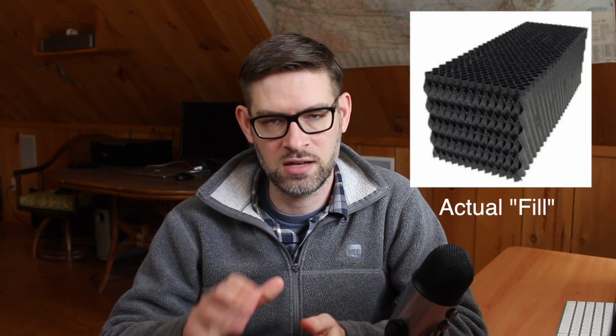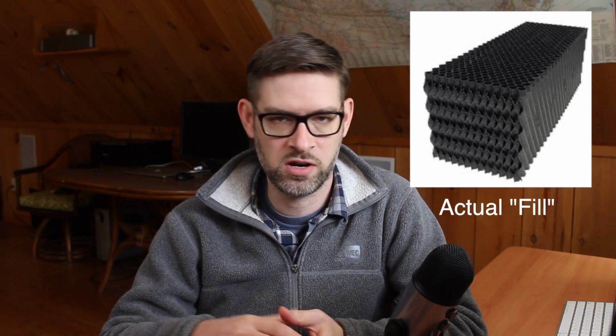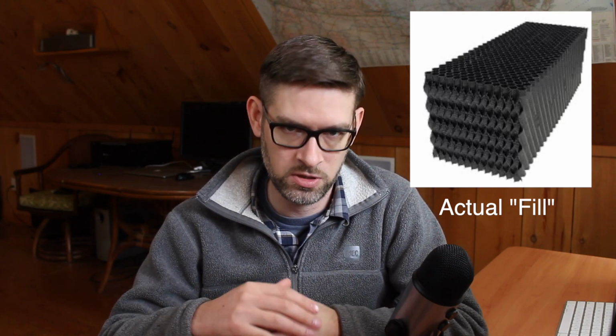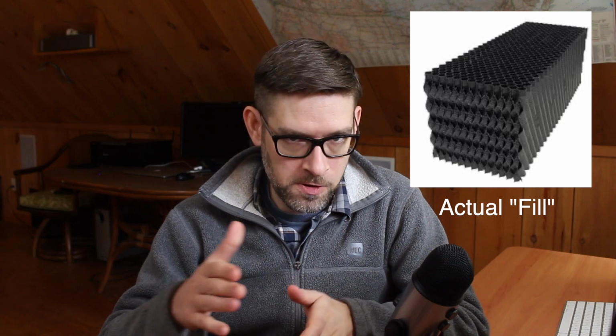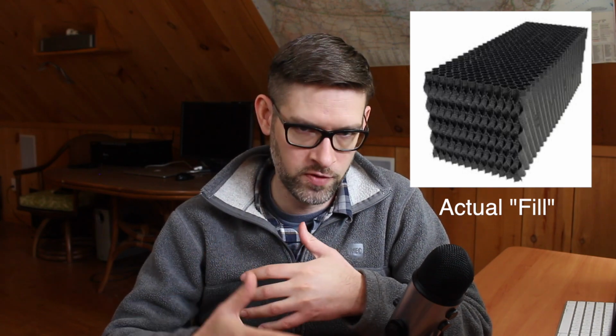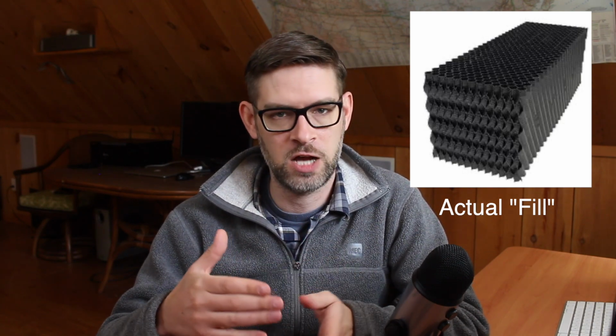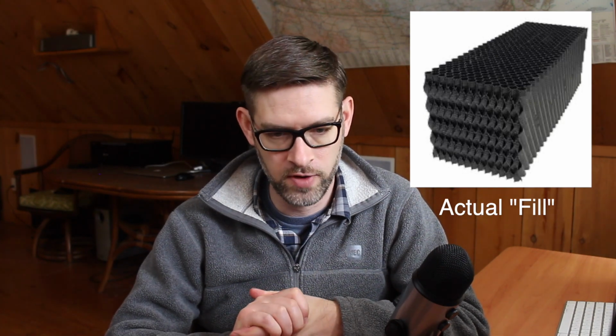Now, the fill most commonly today is a film style fill, and it's designed to provide a large surface area for the working fluid to flow over. A film of water is formed on the surface of that fill, which allows for the most efficient transfer of energy. The tower's spray nozzles above the film are set up to distribute water in an engineered manner to optimize the efficiency of that fill system.